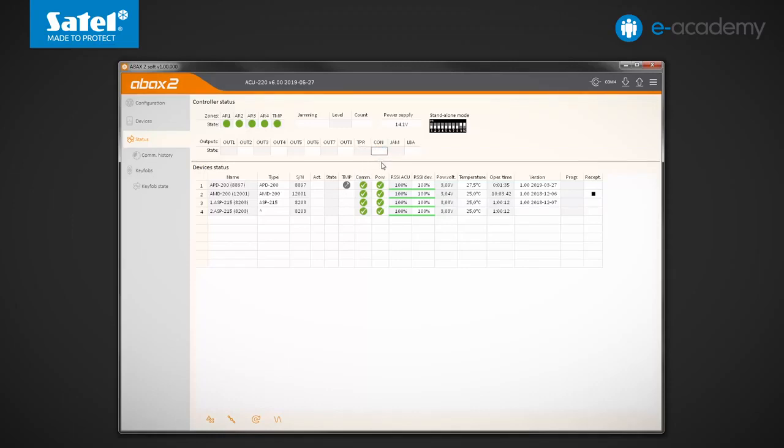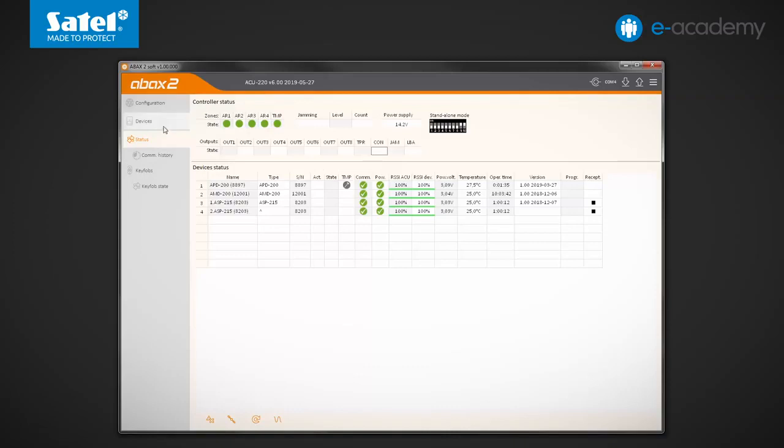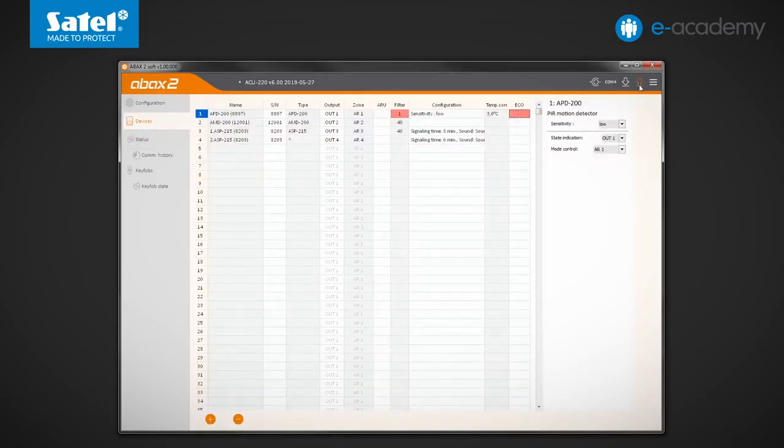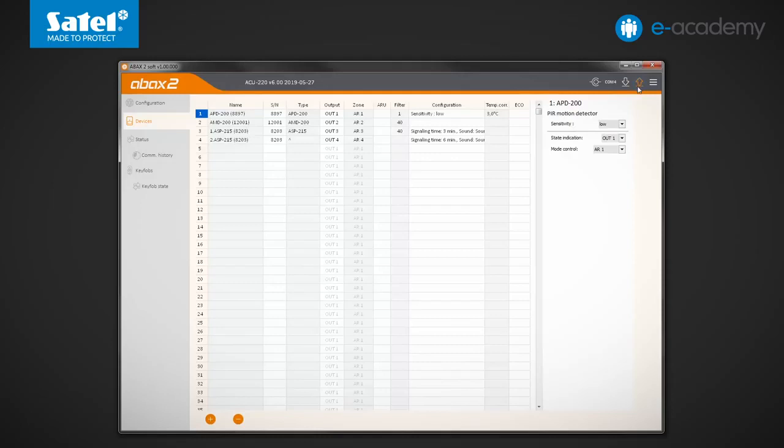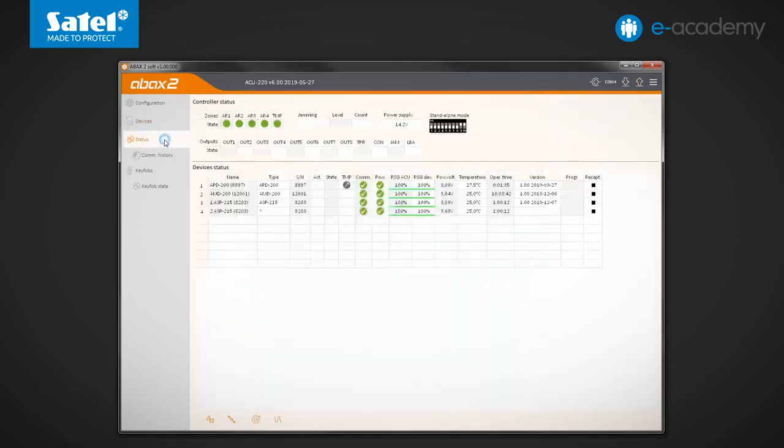The next output is marked as CON. It indicates that there is a communication loss with wireless devices. To check how it works, let's first reduce the time after which loss of communication with the APD200 motion detector will be reported. To do so, set a filter equal to 1 and deactivate eco option. Save the data to the controller and return to the status tab.